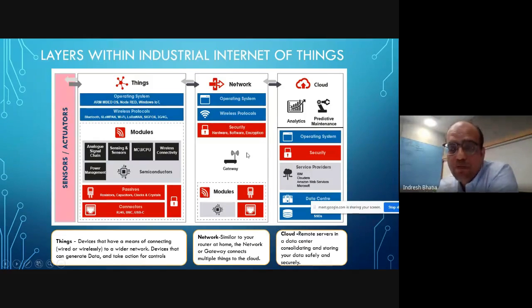You can also convert from one protocol to another. For example, my system supports BACnet protocol, but I still want to get that data on a SCADA. So my communication gateway will convert that BACnet into Modbus that can go up to the SCADA, and from that SCADA, I have APIs which send data to the cloud. So all that conversion of protocols and data happens at this network layer.